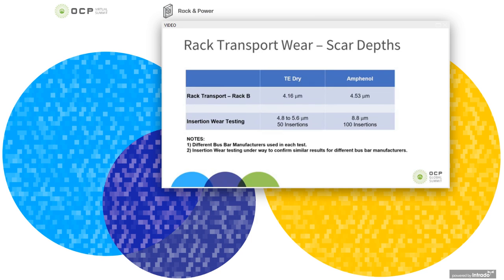But what we're going through right now is some additional insertion wear testing to confirm that the scars we see in the wear testing are similar, in which case the assumption holds true that the rack transport is equivalent to about 50 insertions. So from our point of view, we saw this as, what's the definition of the problem? How deep does the scar get? And can we use insertion wear testing going forward to characterize what happens in rack transport tests? Because it's much easier to do the insertion wear testing than to do the rack transport. Yeah, exactly. Build a test, right? Much easier.